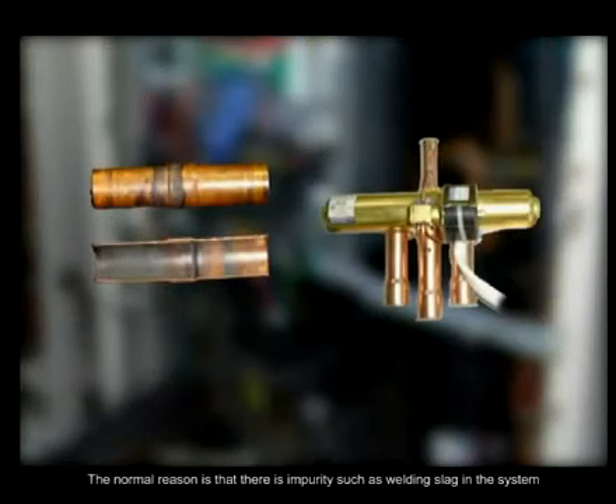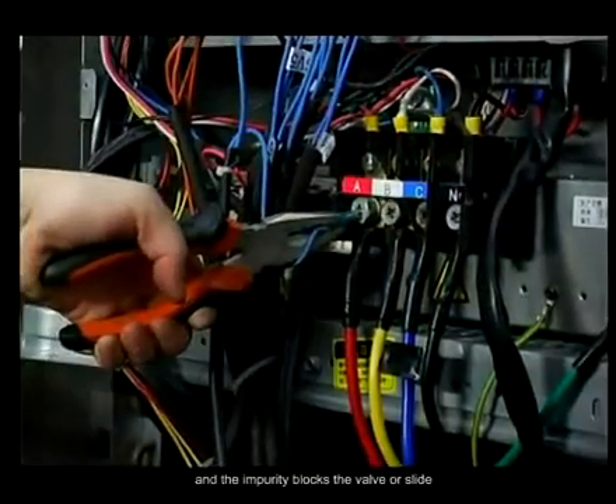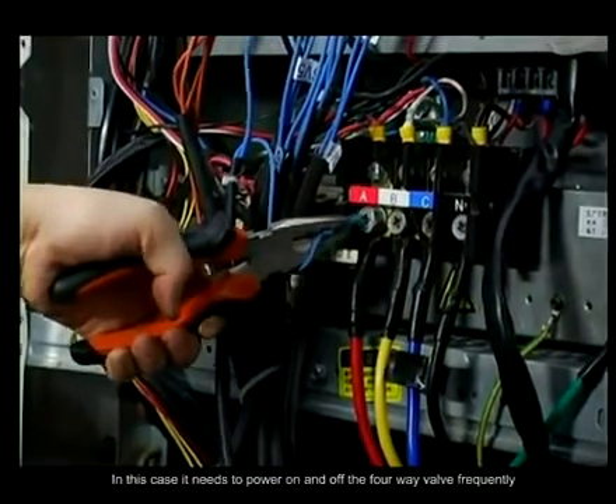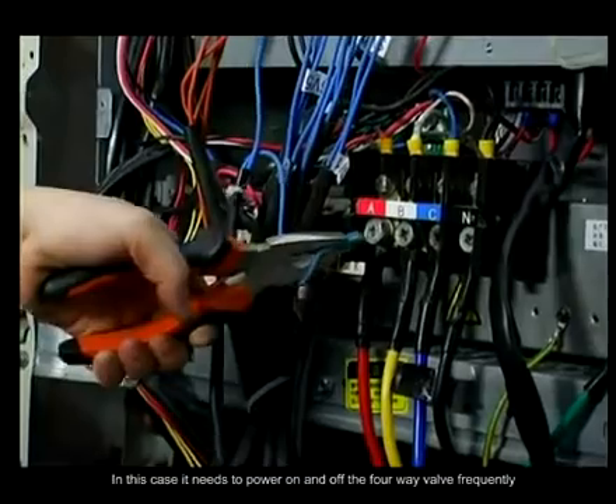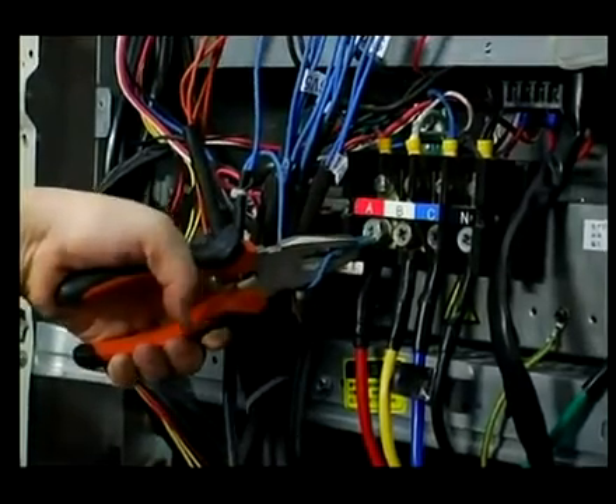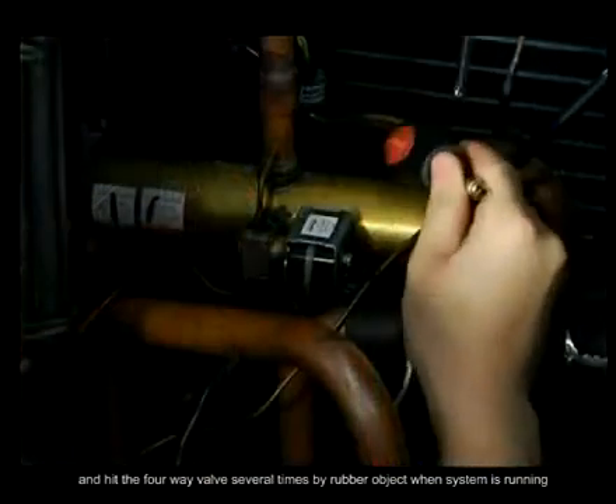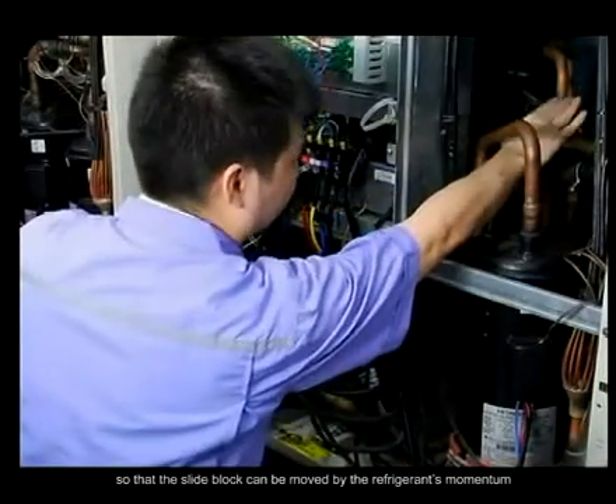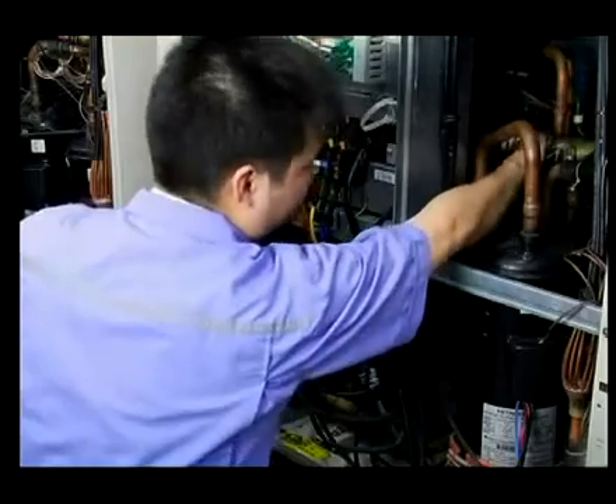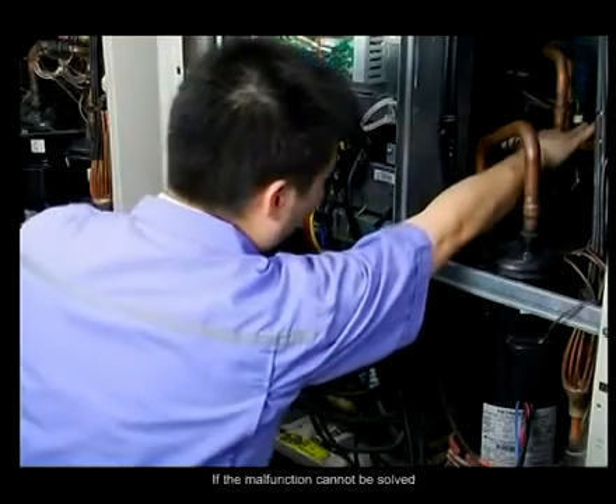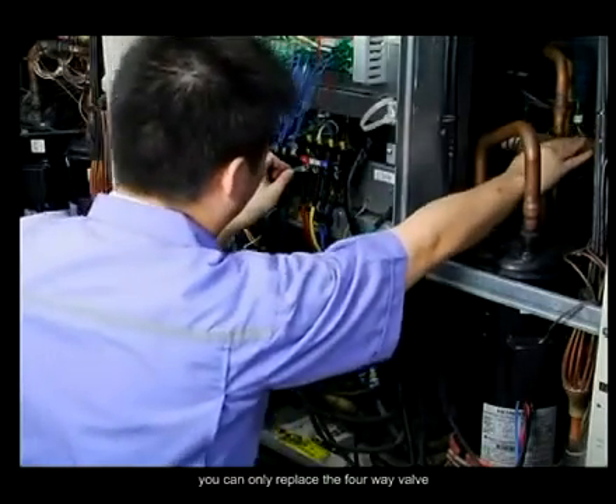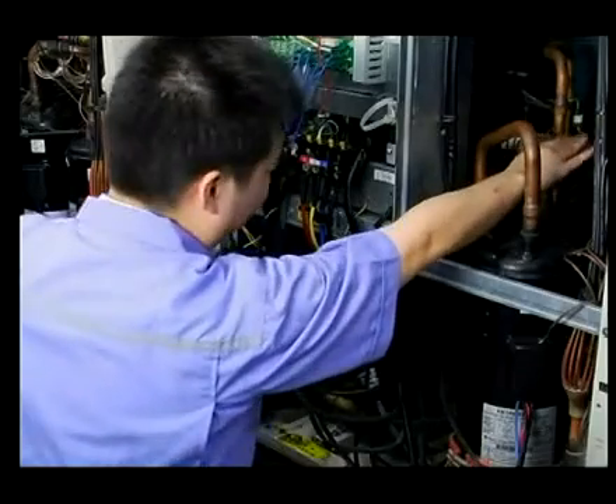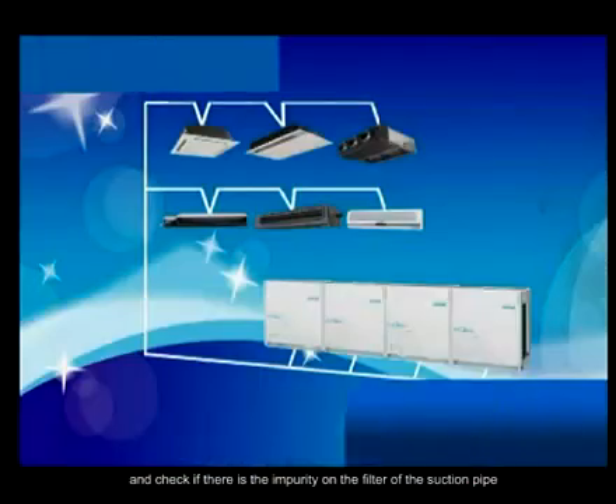The normal reason is that there is impurity, such as welding slag, in the system, and the impurity blocks the valve or slide. In this case, you need to power the four-way valve on and off frequently and hit it several times with rubber objects while the system is running, so that the slide block can be moved by the refrigerant's momentum. If the malfunction cannot be solved, you can only replace the four-way valve and check if there is impurity on the filter of the suction pipe.